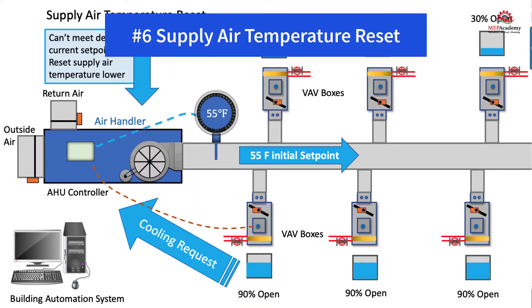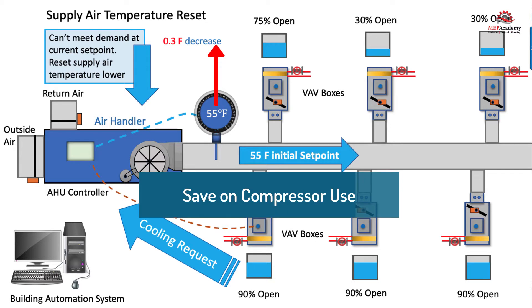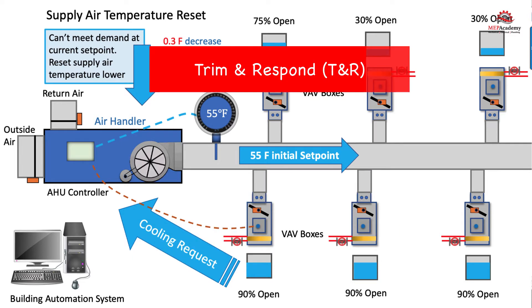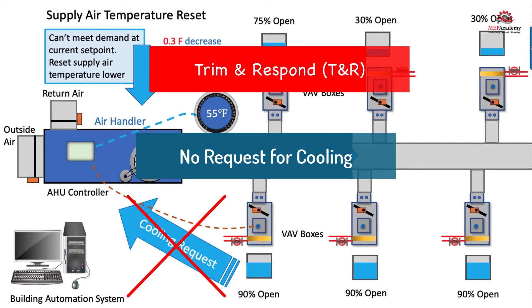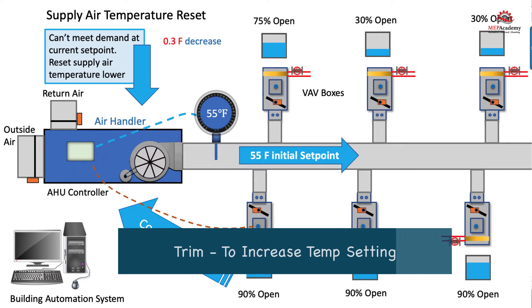Number six: supply air temperature reset. To save energy, the supply air temperature can be reset higher when the demand is reduced. This will save on compressor energy use and allow more time for the use of the air side economizer. Using trim and respond control logic, if no request for cooling is sent to the air handler controller, then the supply air temperature is trimmed by a set value determined by the programmer.